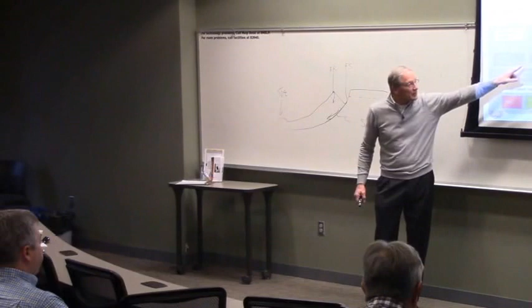We have other microprocessor-based devices in the substation. This is the station controller, or data concentrator, kind of like the master station for the substation. Here we have switches and breakers, sectionalizing devices. We need these to support the logic up above for fault detection, isolation, and restoration. If we want to isolate the fault, we open up switches on either side. That's the logic; this is the actual equipment out on the feeder.